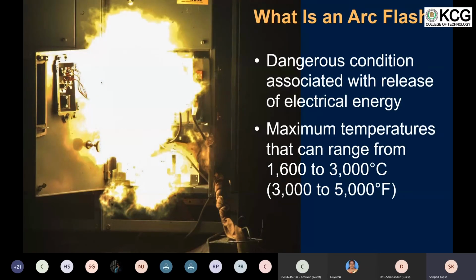We will be talking in this presentation about ways to understand what an arc flash hazard is, and the different approaches typically followed in the industry to reduce arc flash hazard. We will also see how the system I am going to present today can overcome some of the cybersecurity risks associated with the current installations in the industry to mitigate this arc flash hazard. So an arc flash is a dangerous condition associated with the release of electrical energy whenever there is a phase-to-phase fault or a phase-to-ground fault in any power system. Typically, you can expect the temperature of an arc flash to reach up to 3000 degrees Celsius whenever there is an arc flash occurring.